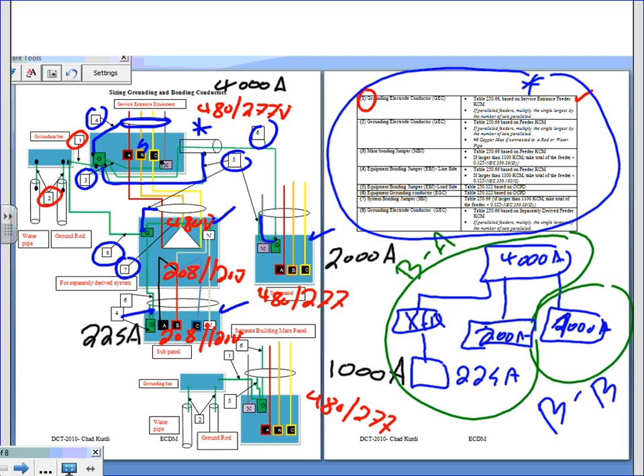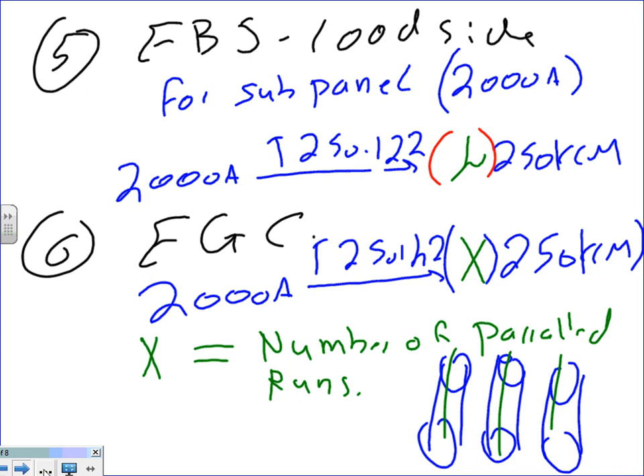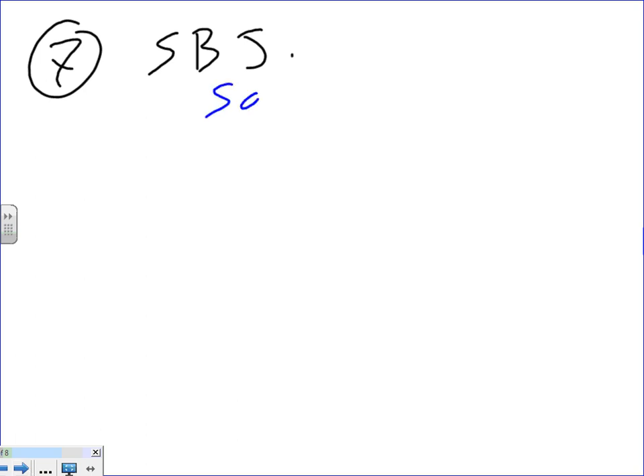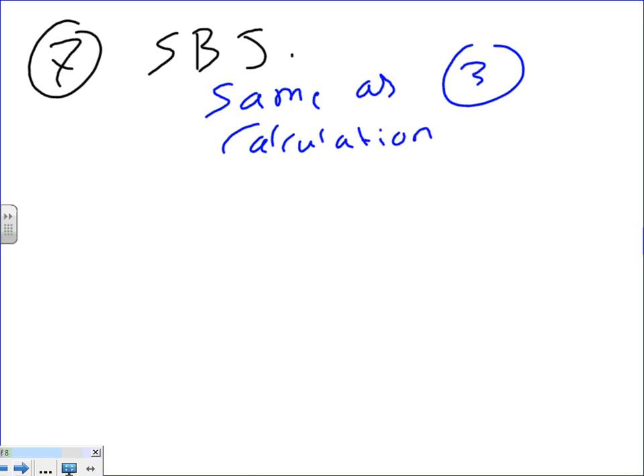Okay? All right, so we size this one. If you guys read based on number 7, it says, based on the largest, blah, blah, blah. So you're going to size it exactly like the number 6. Number 7, with main bonding jumper, same, we call it, what do we call it? System bonding jumper. And I'm going to say here, same as number 3, calculation wise. Same as number 3 calculation, except the calculation is going to be similar, guys, but the feeder is going to be different. Okay, same calculation, same concept.